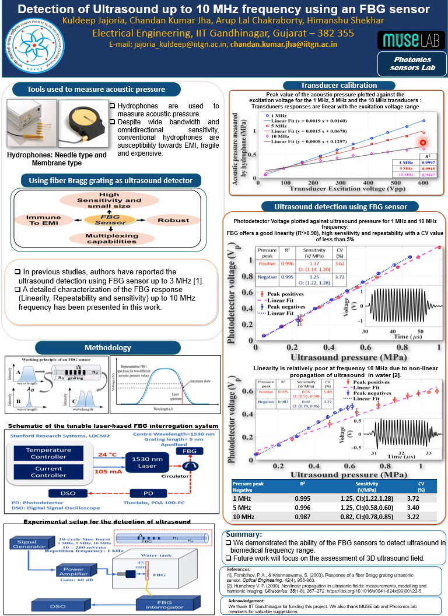of ultrasound pressure. Experiments were then performed, first aligning the FBG sensor with the transducer until we get the maximum signal on the photodetector. The transducer excitation was varied and the corresponding photodetector voltage was recorded. These experiments were done at three different frequencies with their respective transducers. Graphs were plotted of the photodetector voltage against ultrasound pressure.